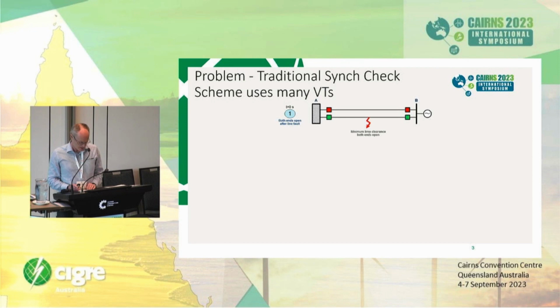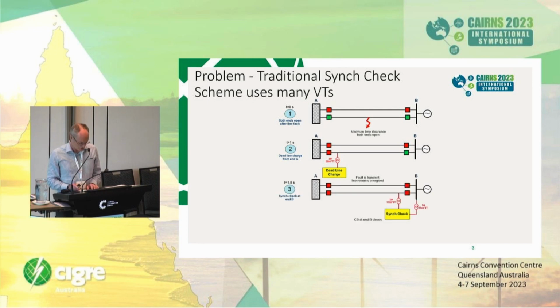A problem with traditional synchronism check schemes is that they are dependent on many voltage transformers being installed. I will describe the stages of Transpower's traditional scheme. First, circuit breakers at each end of the transmission circuit open following a fault. Then, a three-phase line VT at the same end is used to check the line is dead to allow the system end circuit breaker to close and charge the line. Then at the non-system end, line and bus VT voltages are compared for synchronism. If synchronism is maintained, the non-system circuit breaker is closed to restore the circuit.